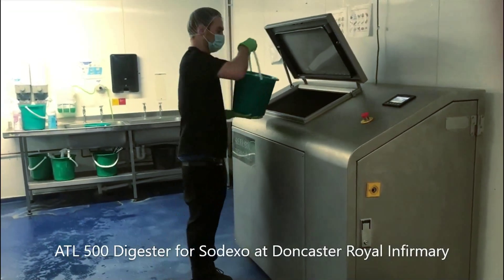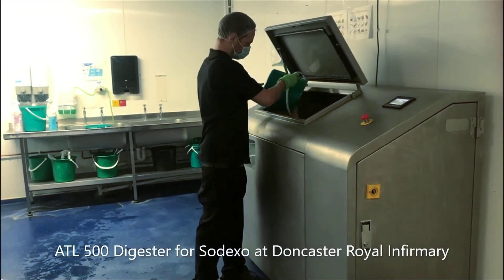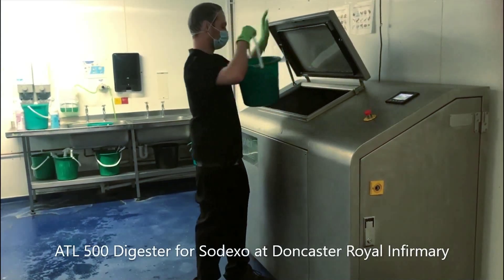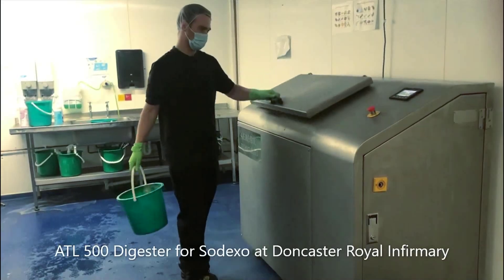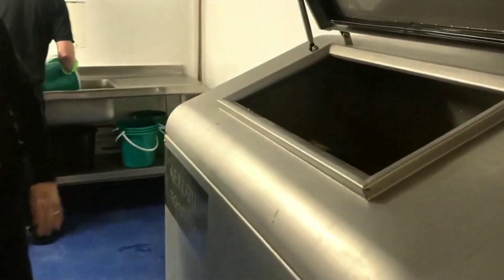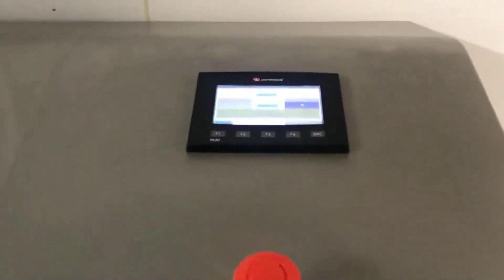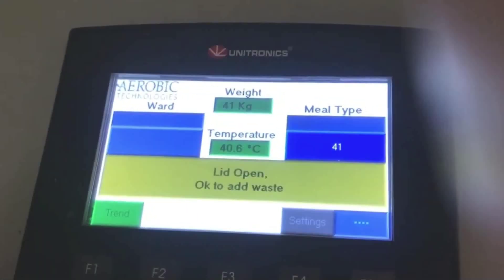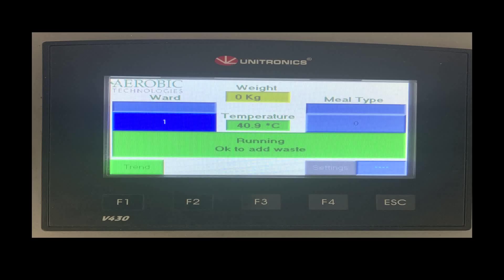The ATL food waste digester utilises four load cells located on each corner to monitor the amount of food waste deposited each time the lid is opened and closed. These load cells transfer the weight information to a Unitronics PLC controller. The function of the PLC controller is to log the data provided by the load cells and also to control the sequence of operations of the agitator motor, the water solenoid valves, and the heaters.